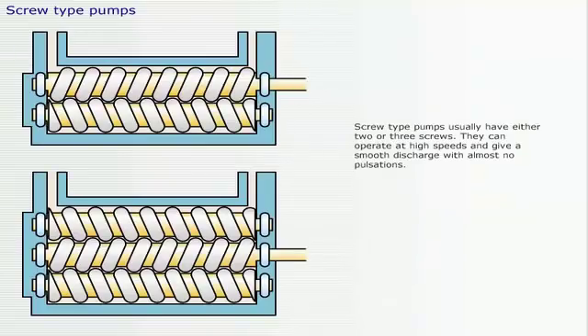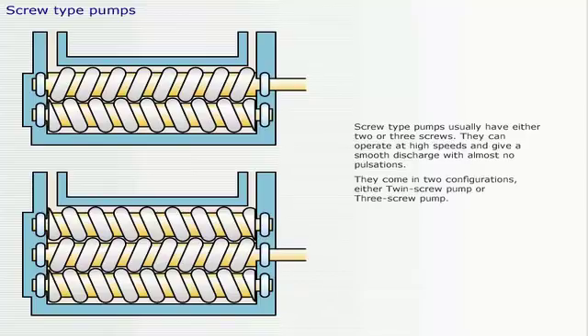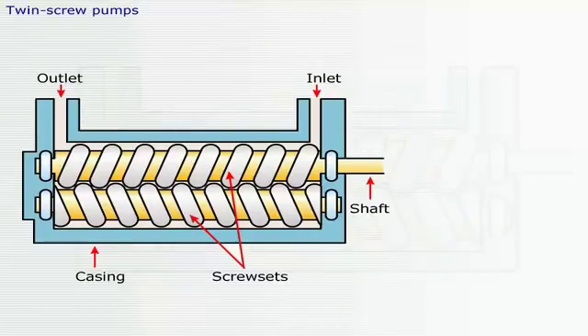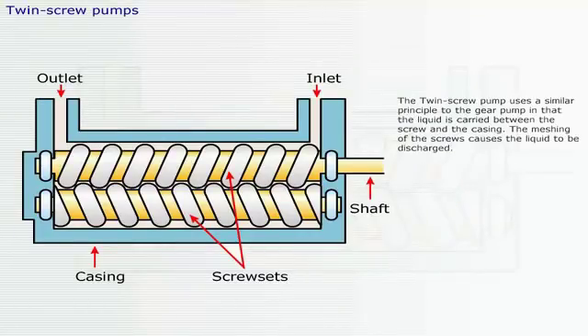Screw type pumps usually have either two or three screws. They can operate at high speeds and give a smooth discharge with almost no pulsations. They come in two configurations, either twin screw pump or three screw pump. The twin screw pump uses a similar principle to the gear pump, in that the liquid is carried between the screw and the casing. The meshing of the screws causes the liquid to be discharged.